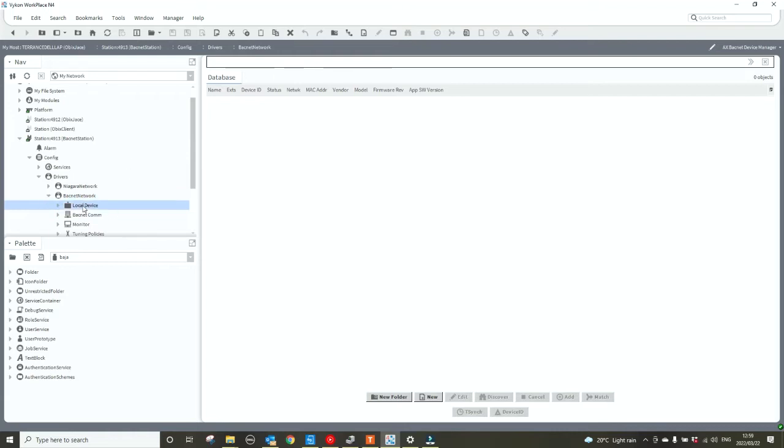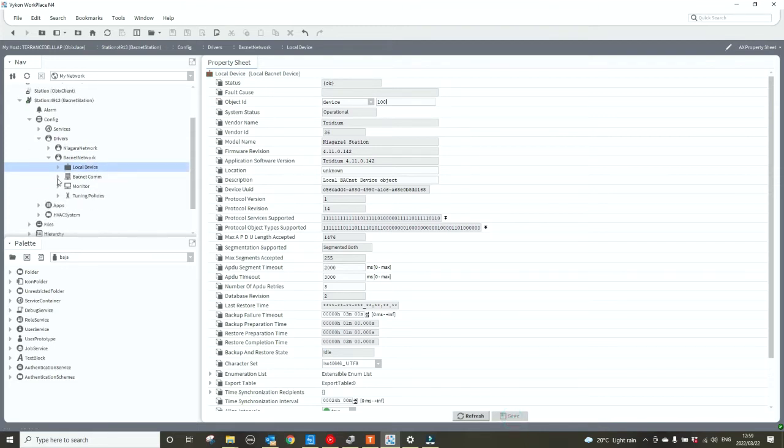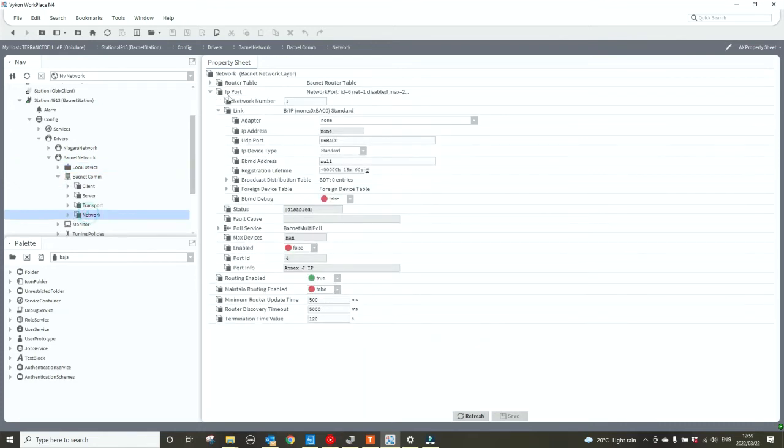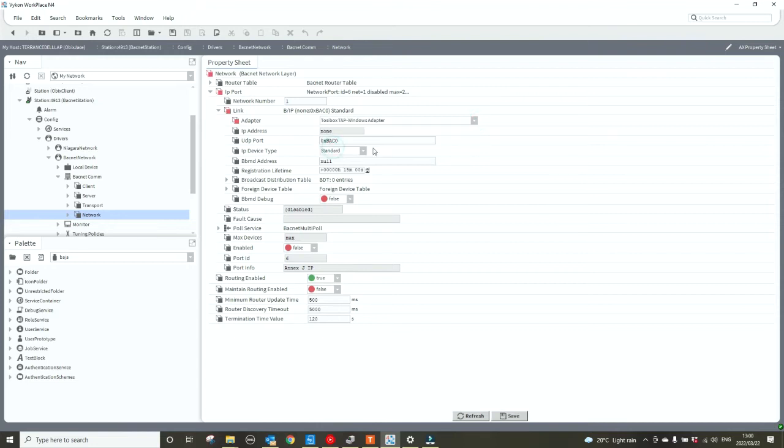The first thing we need to do is set the local device's object ID. In this scenario we're going to give it one of 100, save it. Now I need to go to the BACnet comms to the network and have a look at the network number, that is one. I'll leave it like that for now, and then I need to select the adapter. I'm going to use the Tossibox adapter as I'm doing this demo on my laptop, and I'm going to hit the save button.